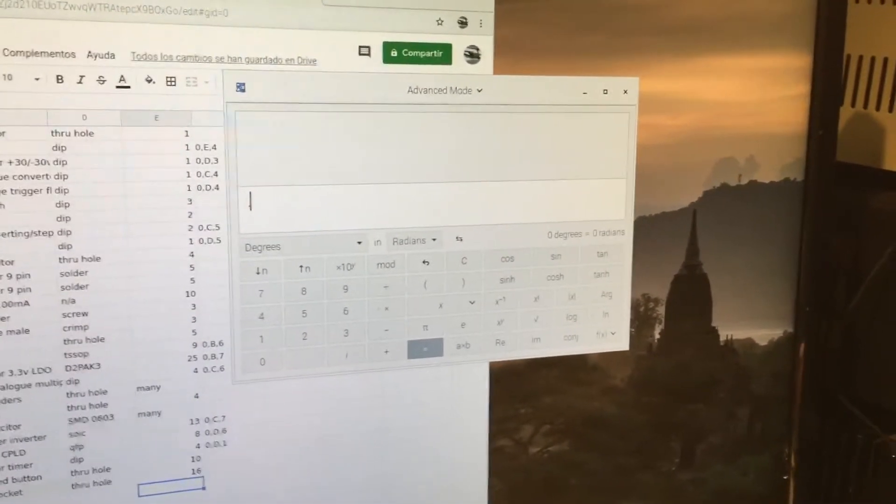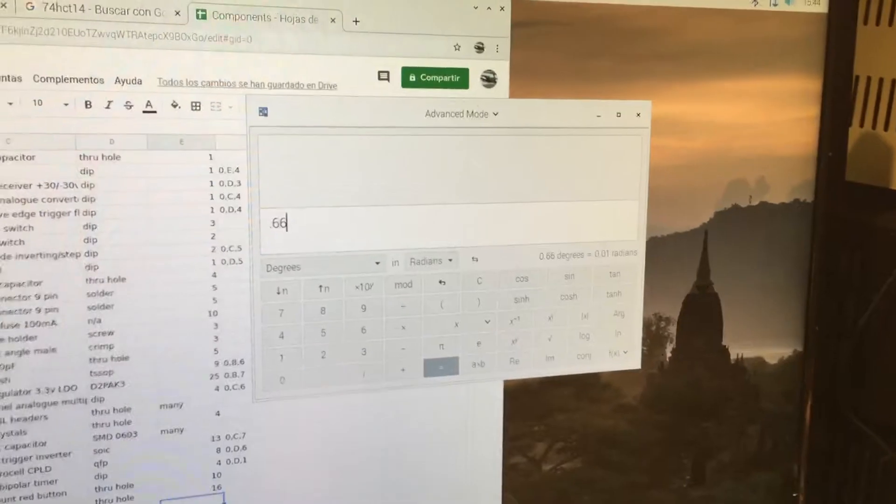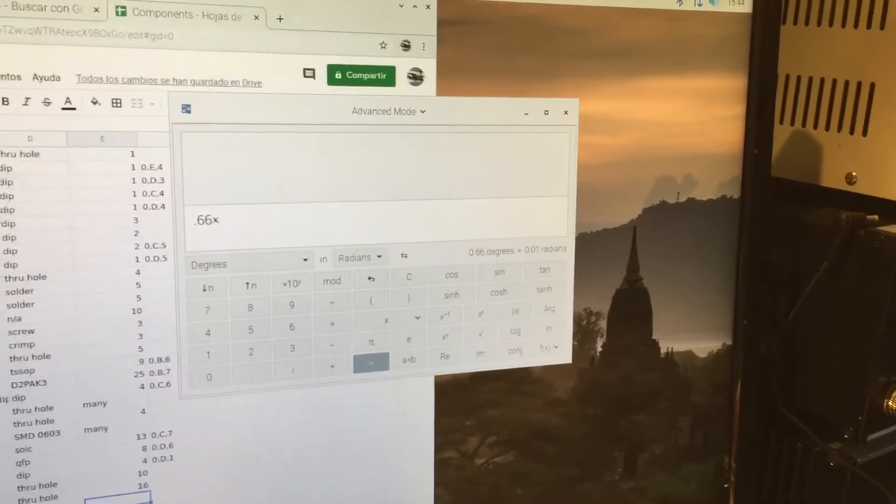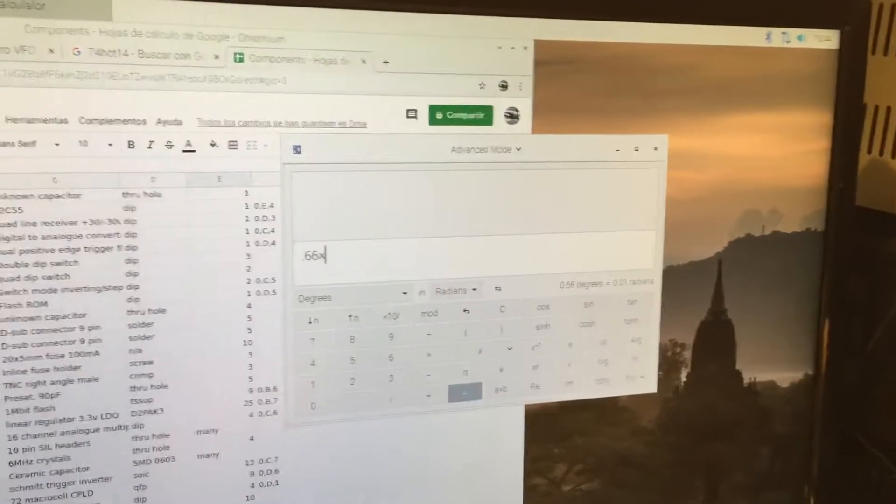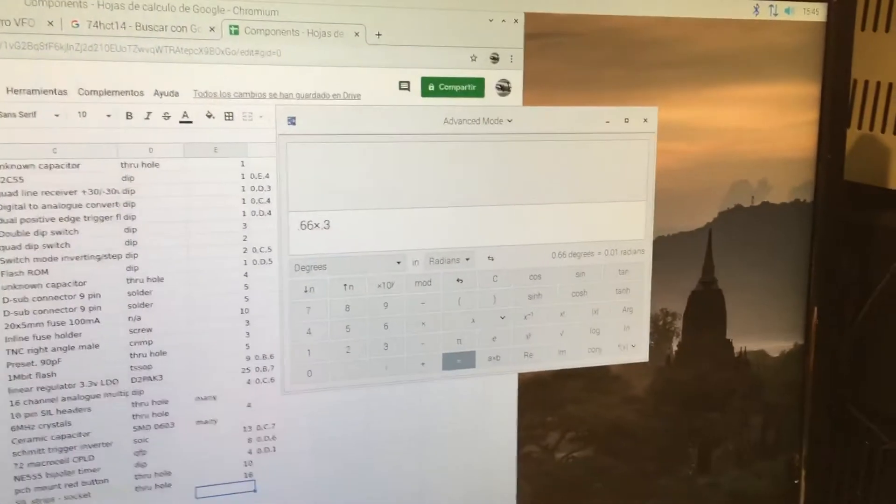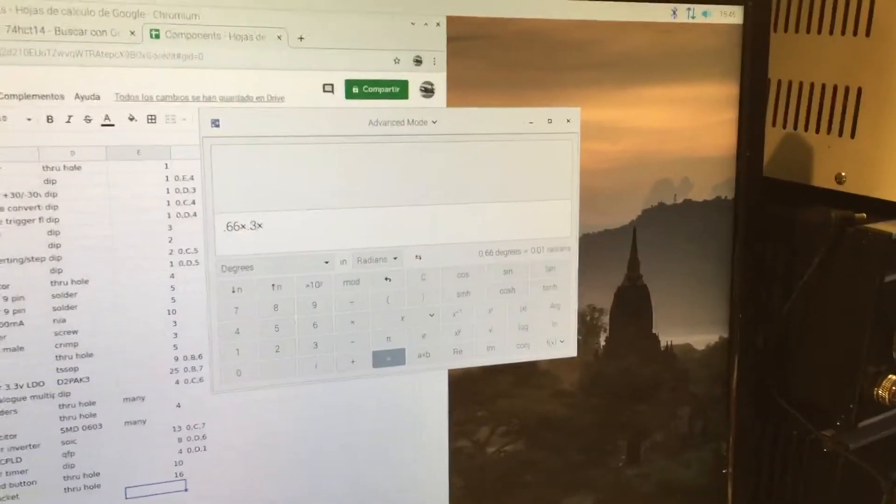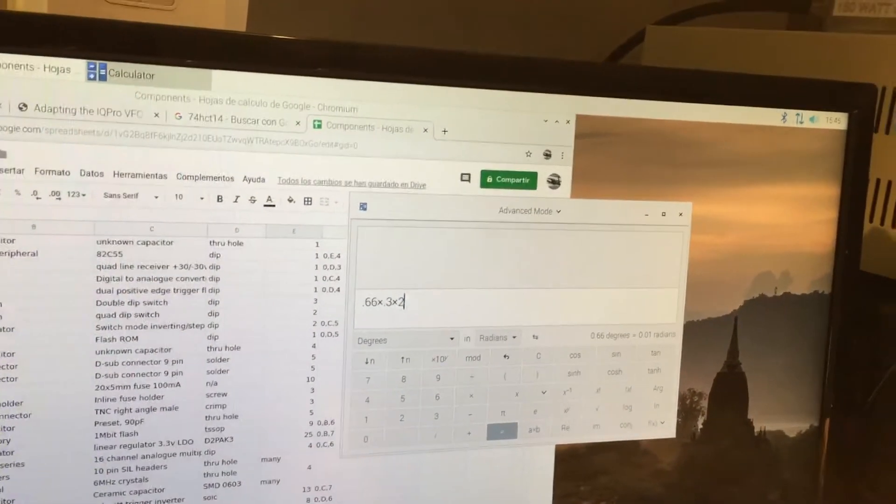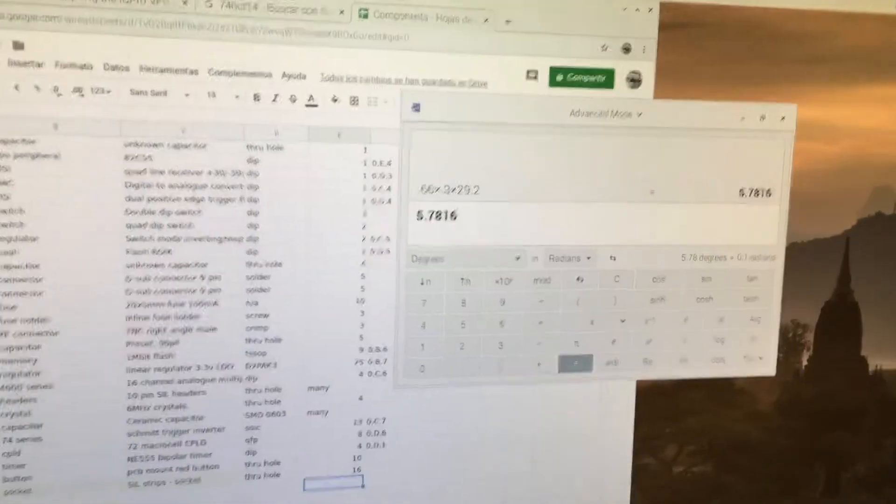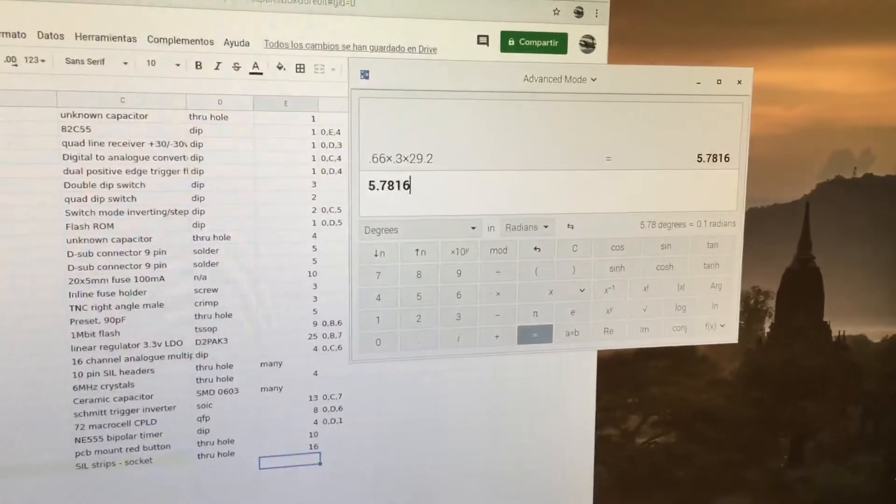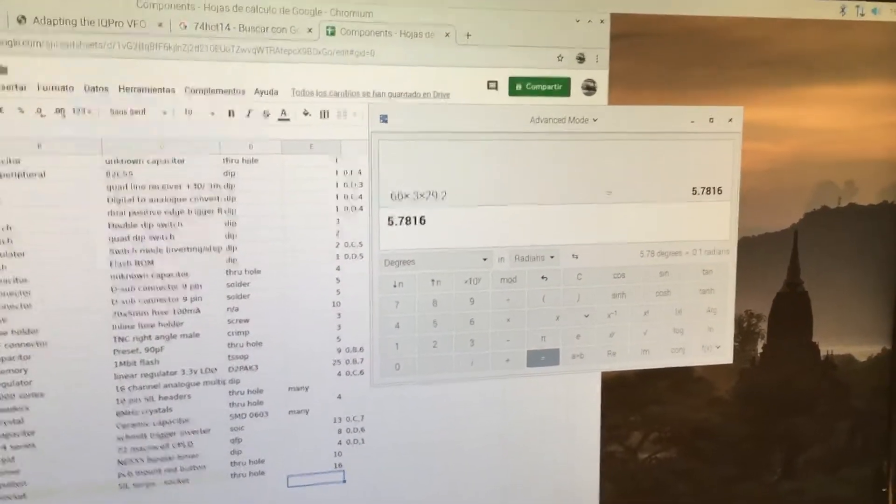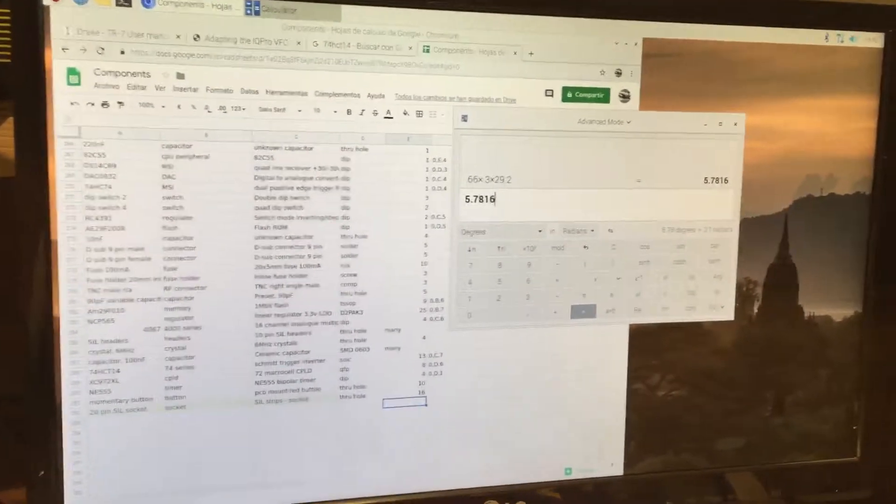If we want the velocity factor of 0.66 times the... we go 0.3 meters is one light nanosecond, and we have 29.2 nanoseconds. That tells us the pulse travelled in the coax for 5.78 meters. And, of course, because of reflection, it's the time it took to go there and come back.